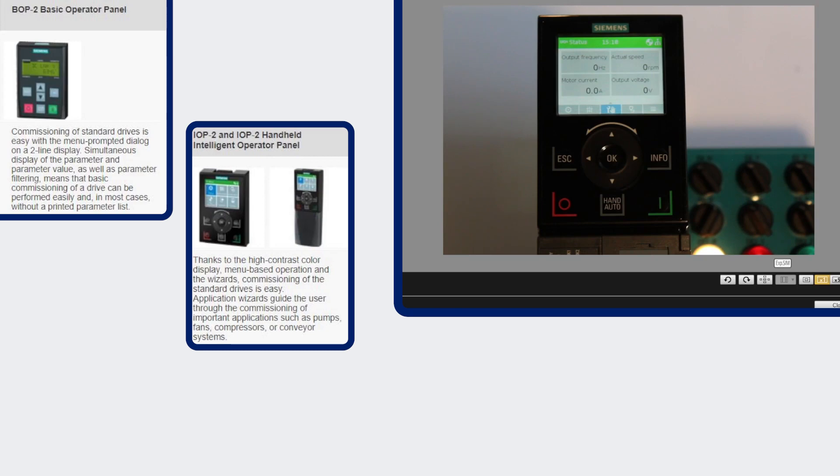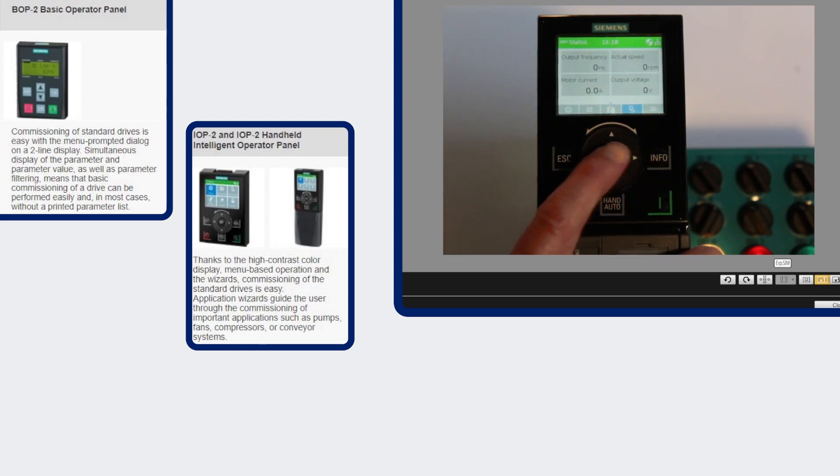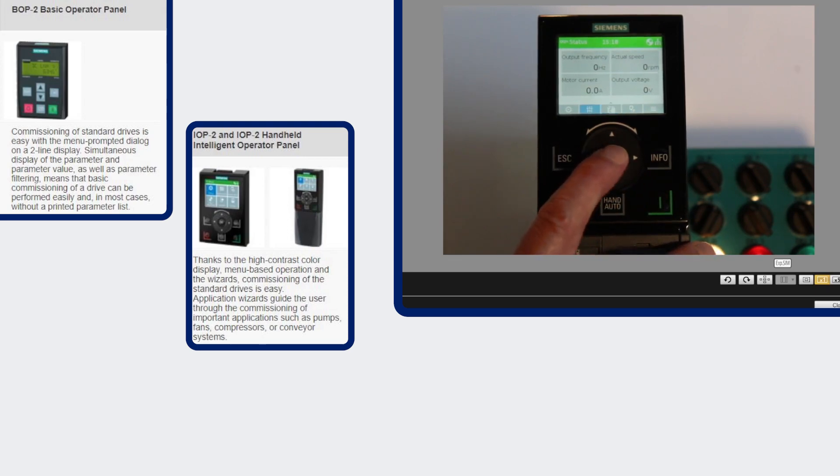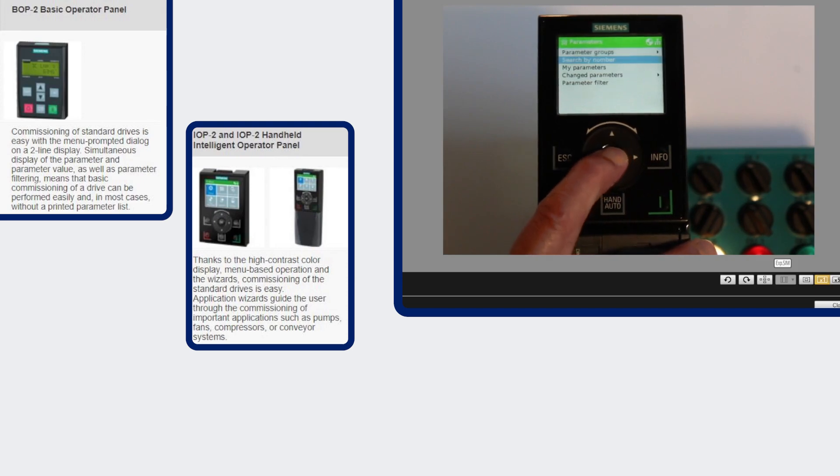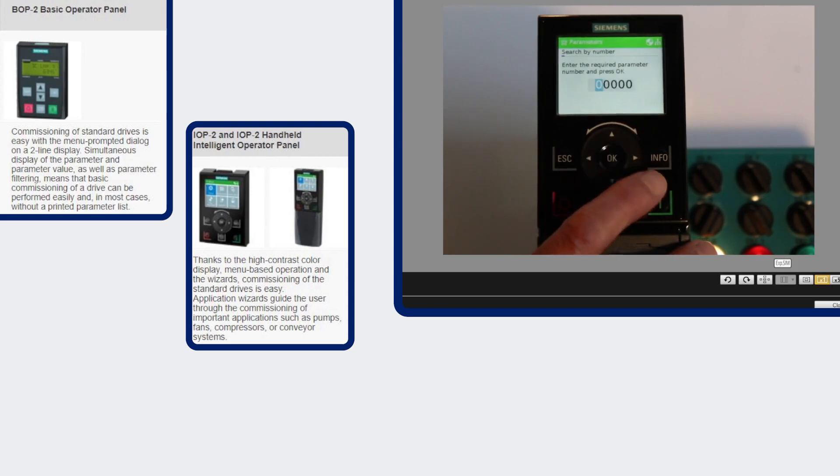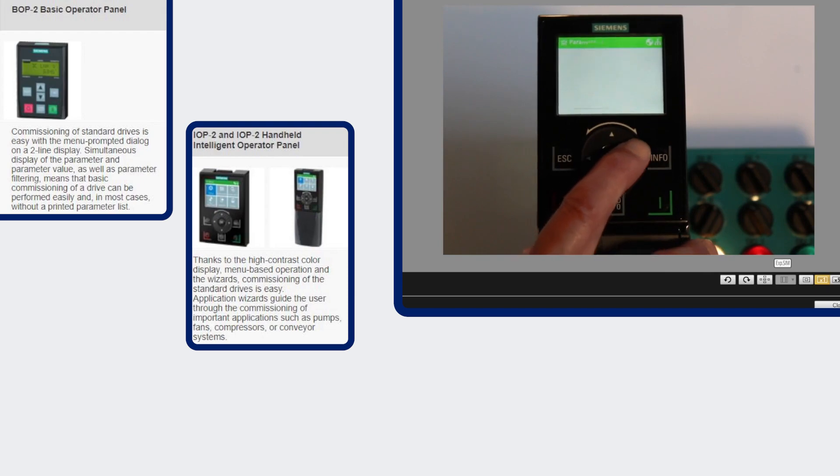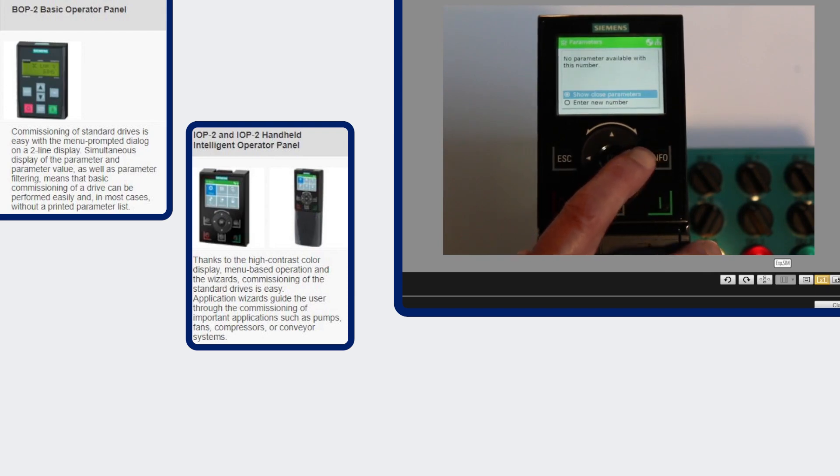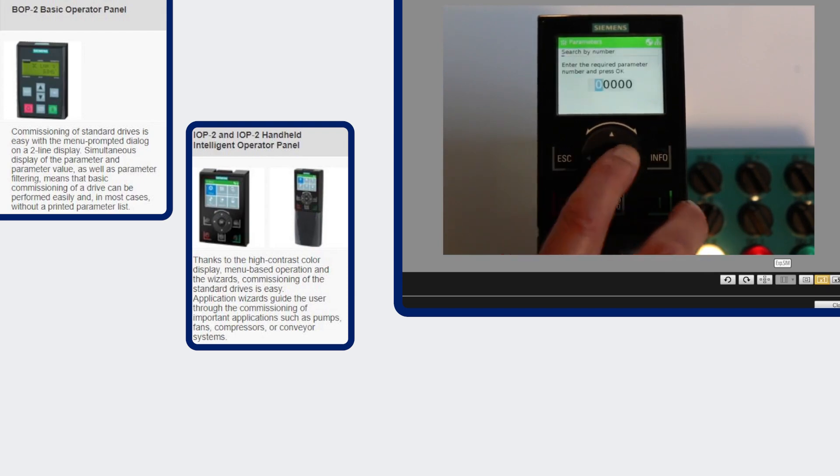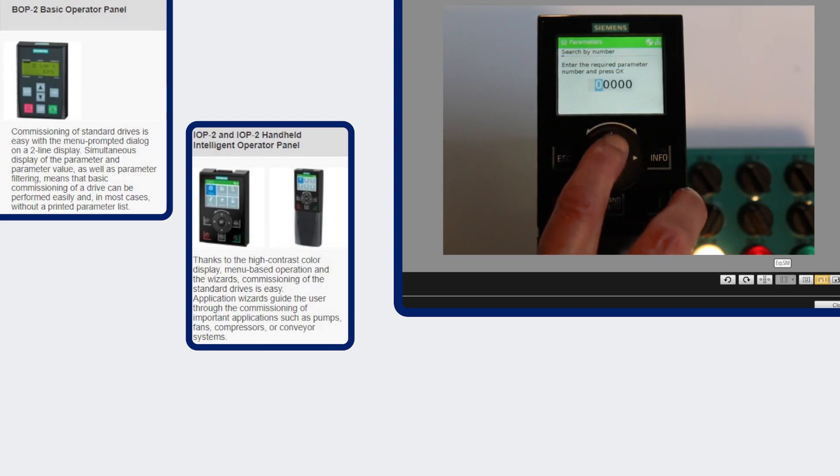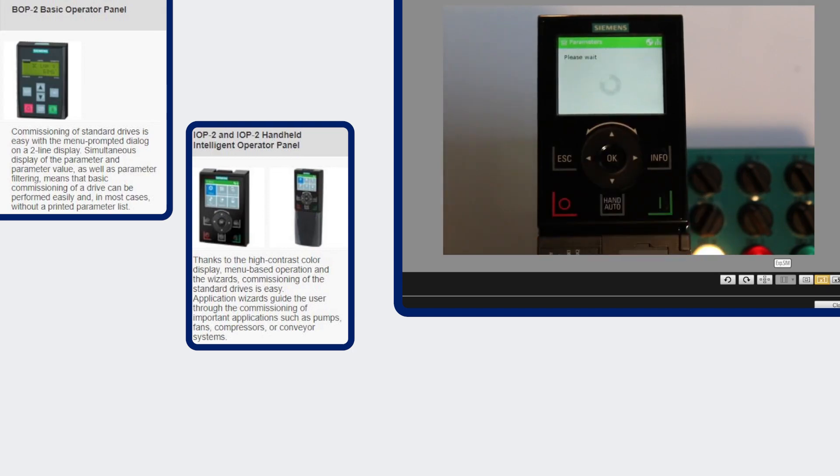It allows you to do quicker commissioning because to change a parameter value you go to the parameter menu and you can enter each individual digit. So instead of having to scroll all the way through, you can just pick a parameter, enter its value, and then it'll bring it up.